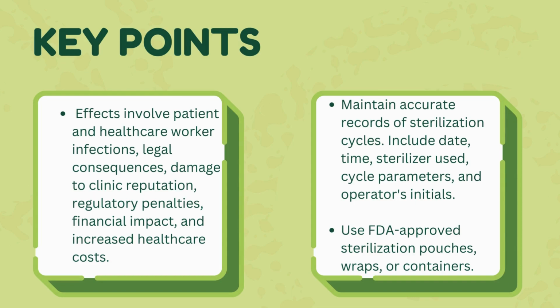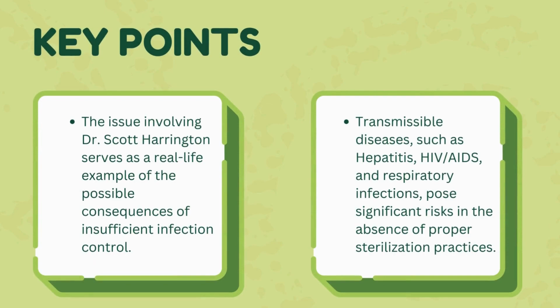Maintain accurate records of sterilization cycles, including date, time, sterilizer used, cycle parameters, and operators' initials. Use FDA-approved sterilization pouches, wraps, or containers. The issue involving Dr. Scott Harrington serves as a real-life example of the possible consequences of insufficient infection control, and transmissible diseases such as hepatitis, HIV or AIDS, and respiratory infections pose significant risk in the absence of proper sterilization practices.